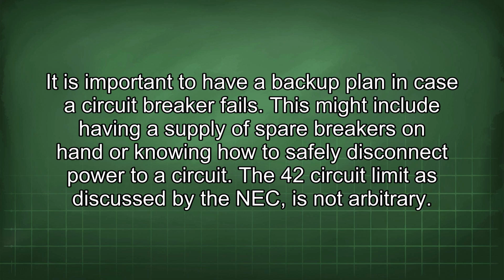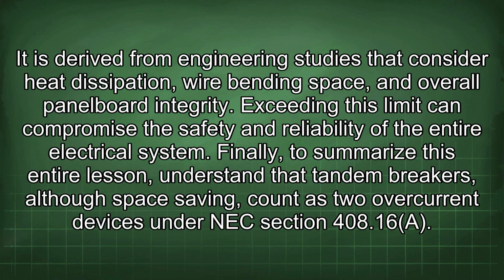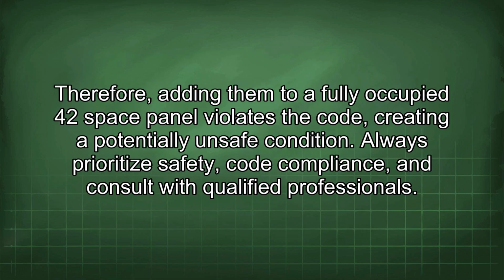The 42 circuit limit as discussed by the NEC is not arbitrary. It is derived from engineering studies that consider heat dissipation, wire bending space, and overall panel board integrity. Exceeding this limit can compromise the safety and reliability of the entire electrical system. Finally, to summarize this entire lesson, understand that tandem breakers, although space-saving, count as two overcurrent devices under NEC section 408.16(A). Therefore, adding them to a fully occupied 42 space panel violates the code, creating a potentially unsafe condition. Always prioritize safety, code compliance, and consult with qualified professionals.